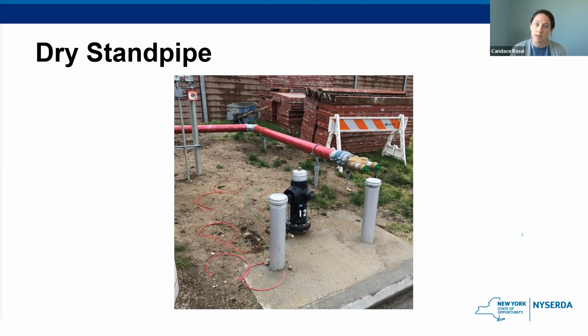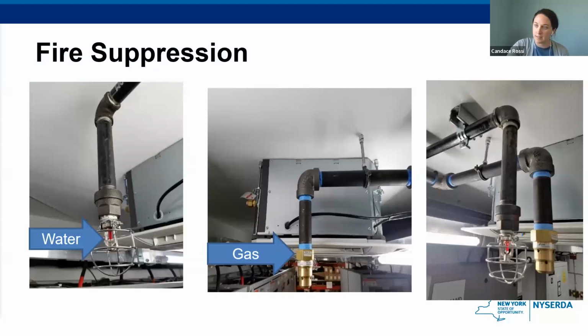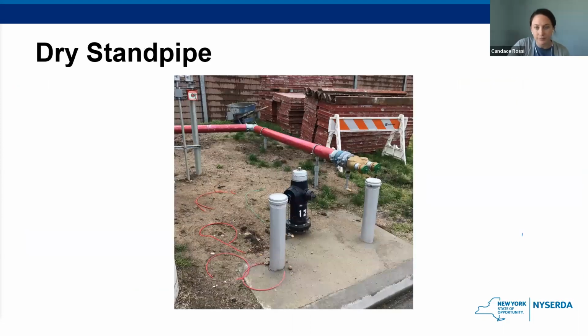And this is once again the same system as the previous slide. Once the fire department hooks up to the standpipe, that is what's being utilized to bring water into the system as well. So via this system, if there is a fire, the water is getting directly in there and will likely flood the entire container.